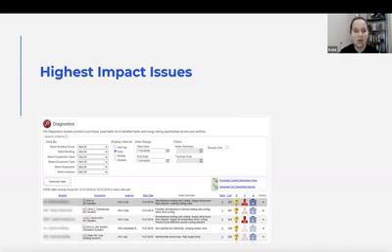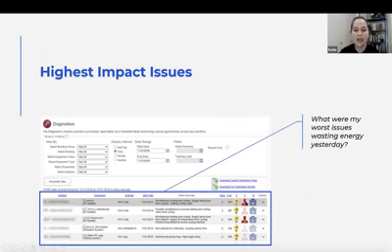So in this case, we're going to come in, we're going to look at our diagnostics across this particular campus. We see that the top 5-6 issues are related to the air handler, and we have one related to the heating system. We are looking at energy, comfort, maintenance scores, and the energy cost associated with the problem.